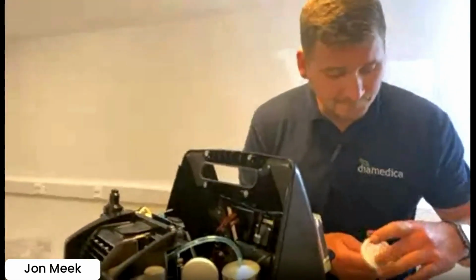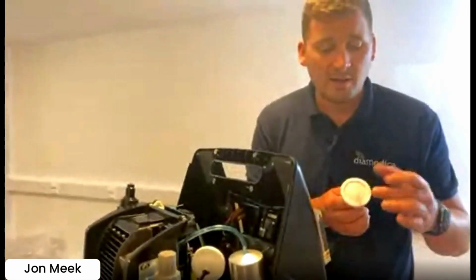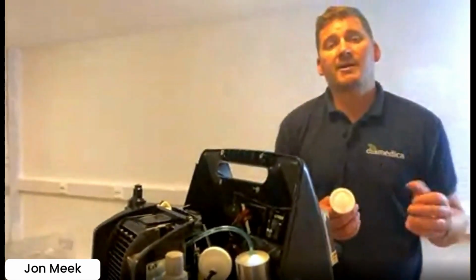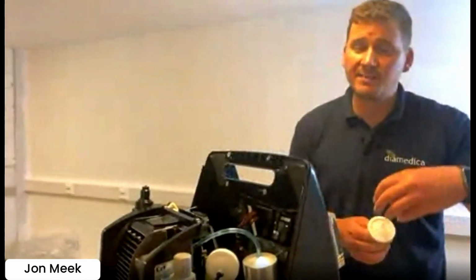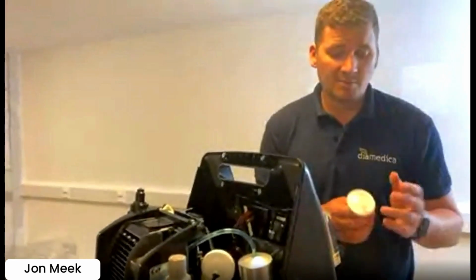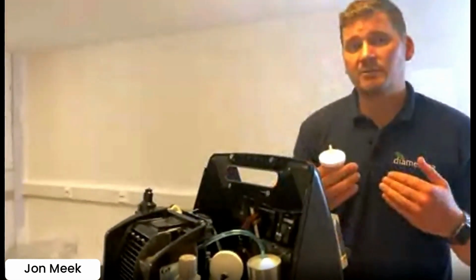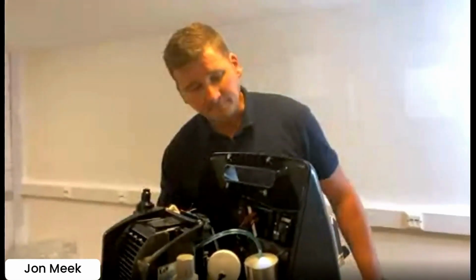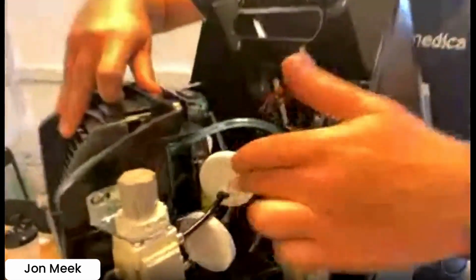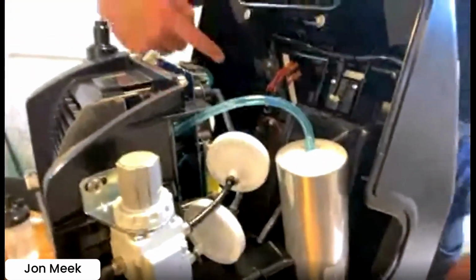When these are gray, that's fine. So when you first start running, they will go gray. When they go black, it means they're starting to become a barrier and they need to be replaced. But like I say, these should be 18 months to 2 years minimum, and should be fine to use. Again, it's all down to the filter and the maintenance before that. So once that comes through from your HEPA filter, it goes into the back, through to your flow meter, and then it goes into the common gas outlet in the middle. Really simple, but really effective on that side.